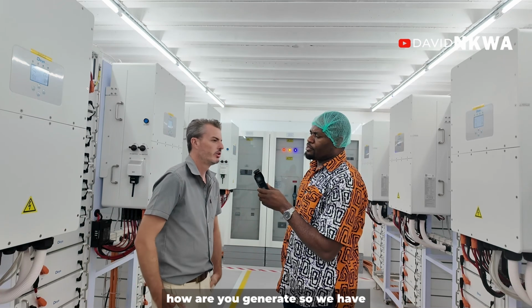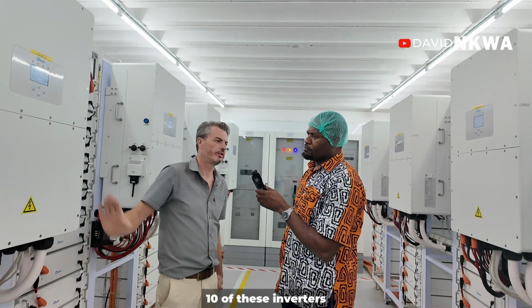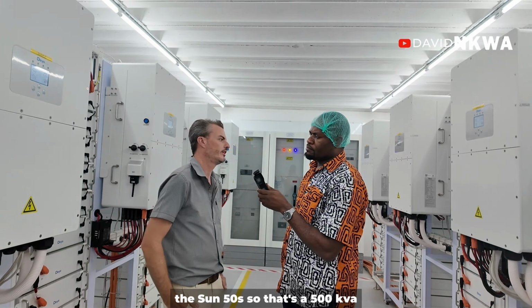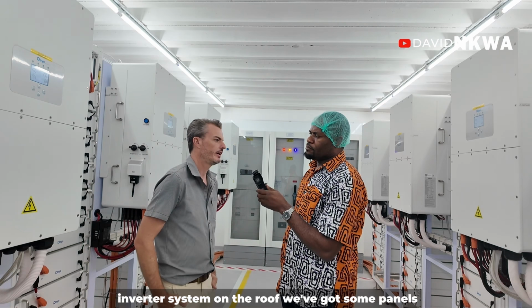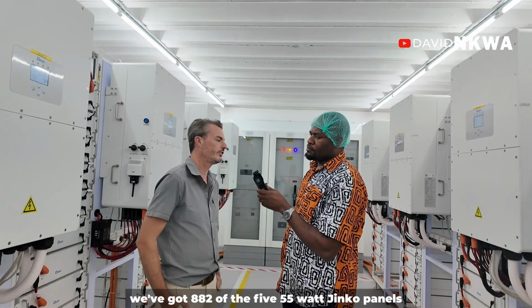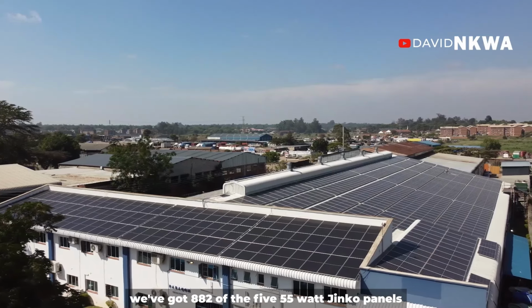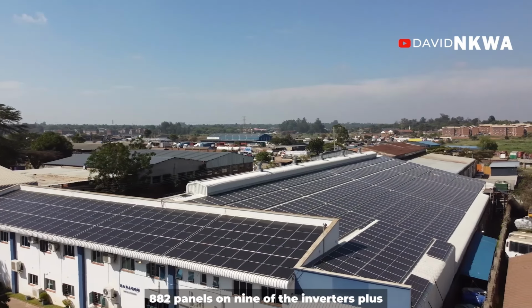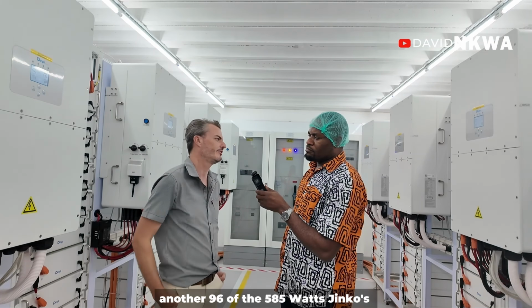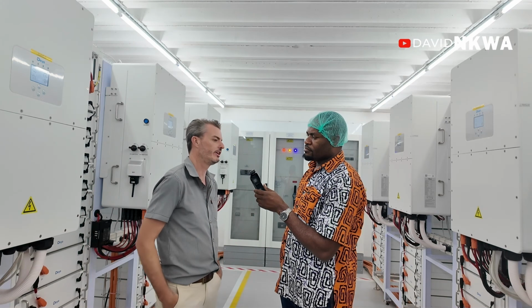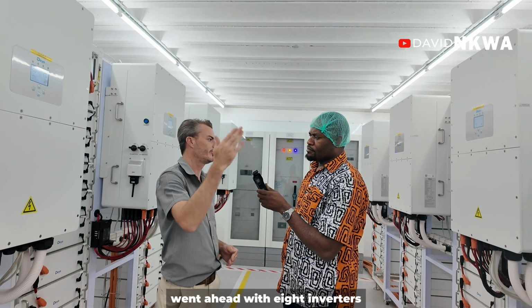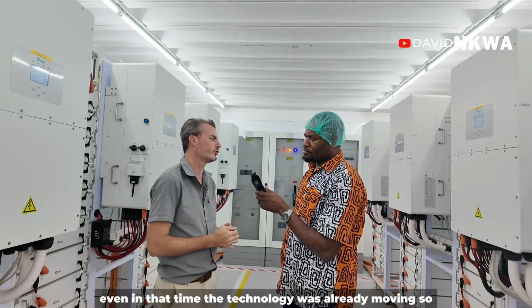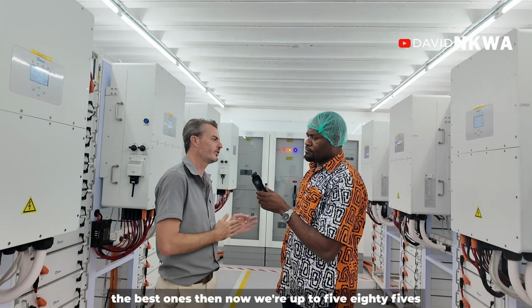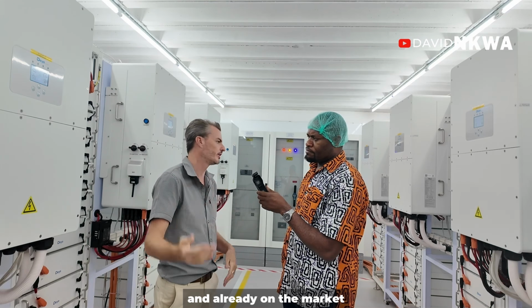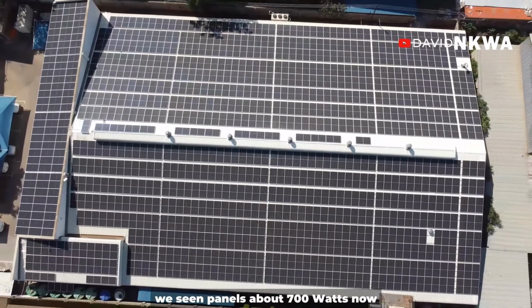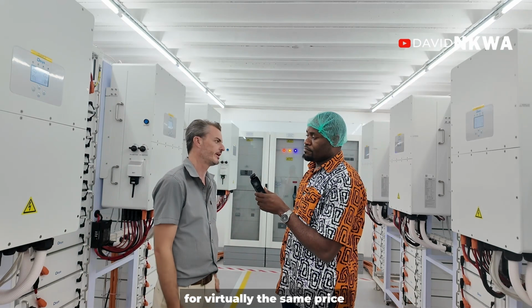How many kVA do you generate, and how? We have 10 of these inverters, the Sun 50s, a 500 kilowatt, 500 kVA inverter system. On the roof we've got 882 of the 555 watt Jinko panels across 9 of the inverters, plus another 96 of the 585 watt Jinkos. Even within that timeline we went ahead with 8 inverters, then added a 9th and 10th, and even then the technology was already moving—555s were the best then, now we're up to 585s, and already panels above 700 watts are readily available on the market for virtually the same price.